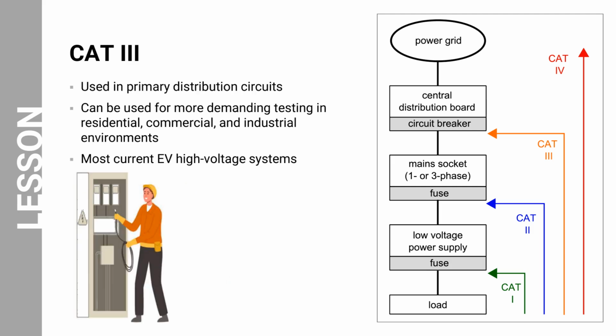appliances, portable tools, and office and industrial equipment. Cat 3 rating is designed to measure primary distribution circuits used in fixed installations, such as distribution panels and industrial systems. It can be used for more demanding testing in residential, commercial, and industrial environments. Cat 3 equipment provides a higher level of protection than Cat 2. It is also suitable for handling most current BEV high-voltage systems.